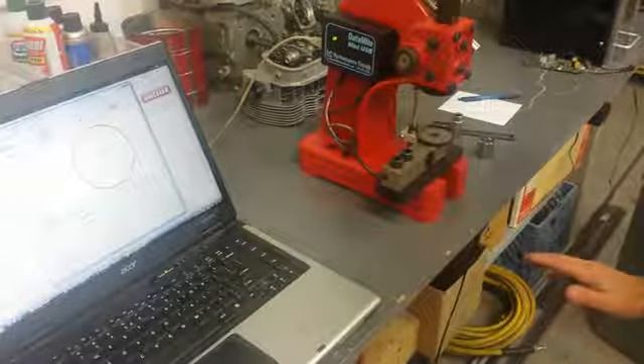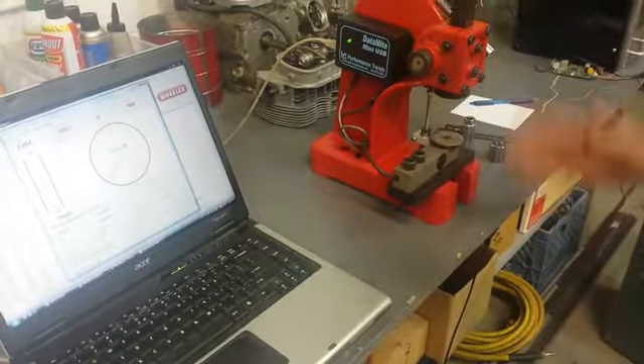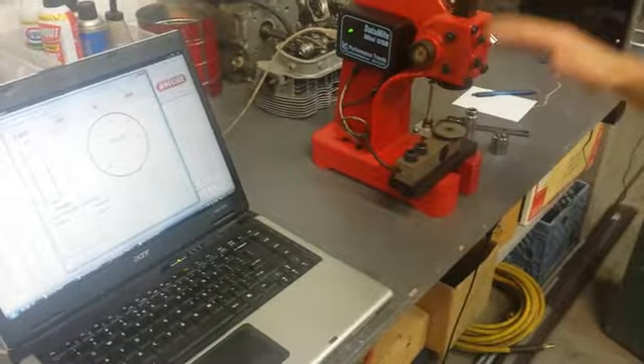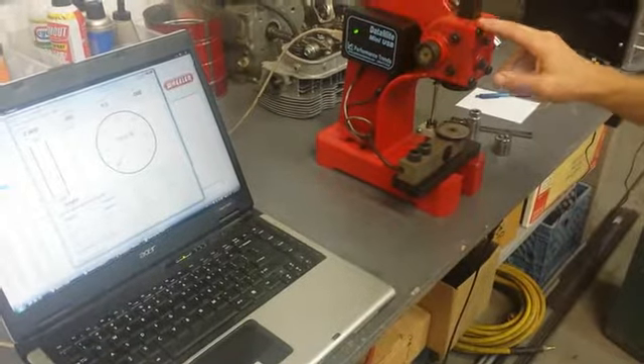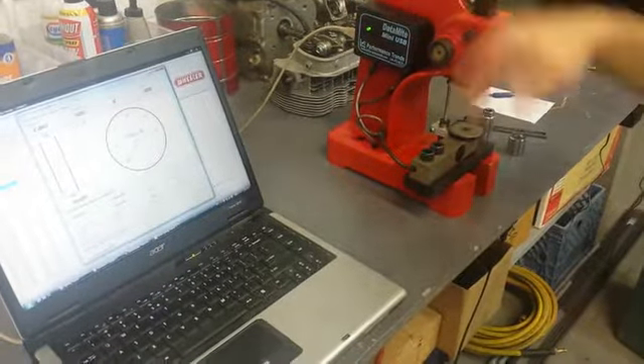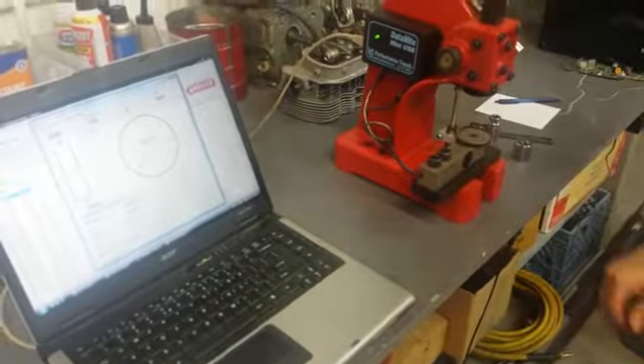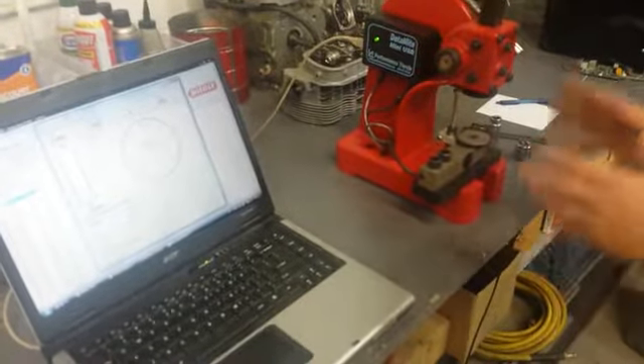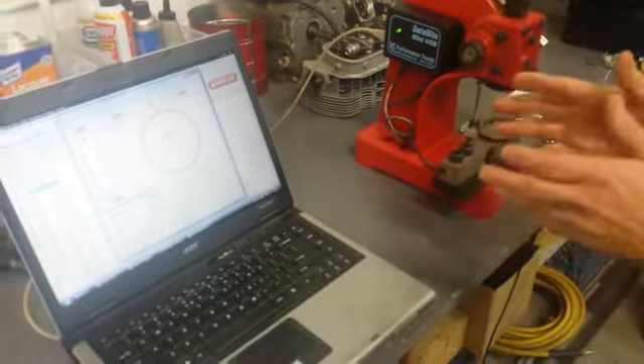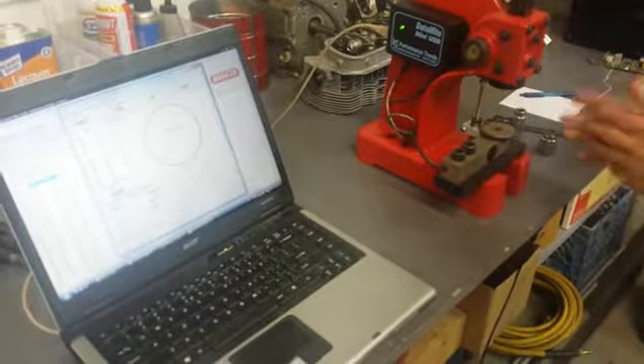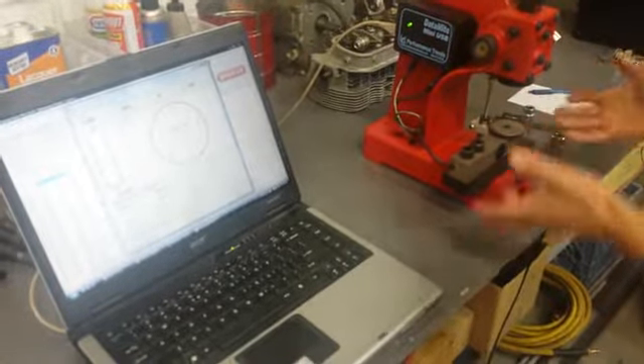What we're going to talk about today is doing a basic calibration. What we're going to use for our test piece is an old PowerTech spring tester that a customer has put our retrofit kit on with our Datamite Mini. What calibration means is, how do you make the computer, which is reading volts, make some sense out of it, like in inches or pounds of force?